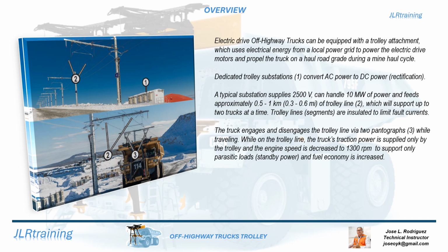Dedicated trolley substations: 1. Convert AC power to DC power, rectification. A typical substation supplies 2,500 volts, can handle 10 megawatts of power, and feeds approximately 0.5 to 1 kilometer, 0.3 to 0.6 miles, of trolley line. 2. Which will support up to 2 trucks at a time. Trolley line segments are insulated to limit fault currents. The truck engages and disengages the trolley line via 2 pantographs.